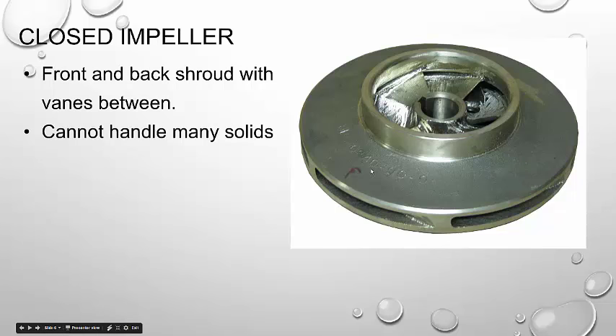The spacing here, we're going to have a critical spacing here which basically decides how much solids is going to be allowed through these things. And typically we're looking at very clear water, irrigation water, and even more specific, I'm going to maybe even want screened water at the bottom if I have even any sand because these things are very, very efficient. However, very small passage of solids through them.